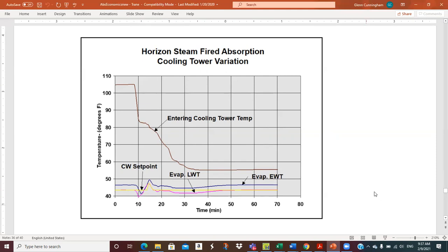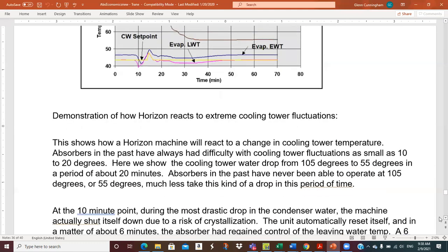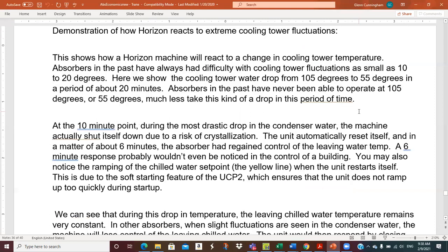So initially it goes down and then it comes up. Well, I think they say there's a 6-minute period here where the machine is just shut down. It just doesn't feel like it can deal with it. And then it brings it back online and ramps it up slowly. And you can see the evaporator leaving water temperature has a little spike here, and that's the result, I think, of the machine being down. And then they ramp this down a little bit slowly so that they don't just go crazy. And I don't know, we can look and see. This first paragraph, they're just talking about what they did. At the 10-minute mark, most drastic drop in condenser water, the machine actually shut itself down due to risk of crystallization.